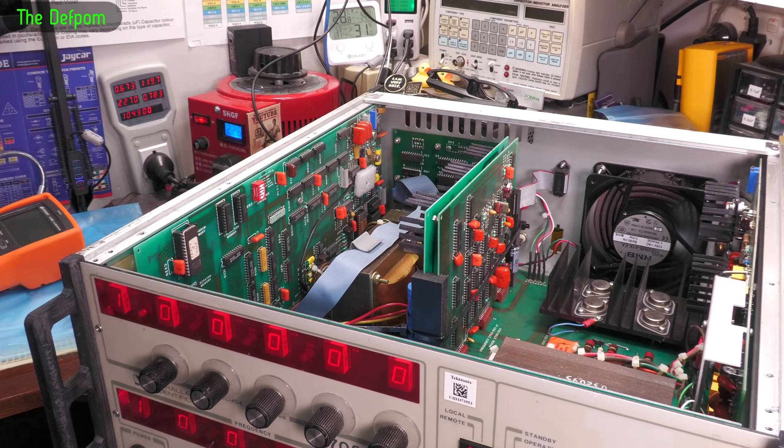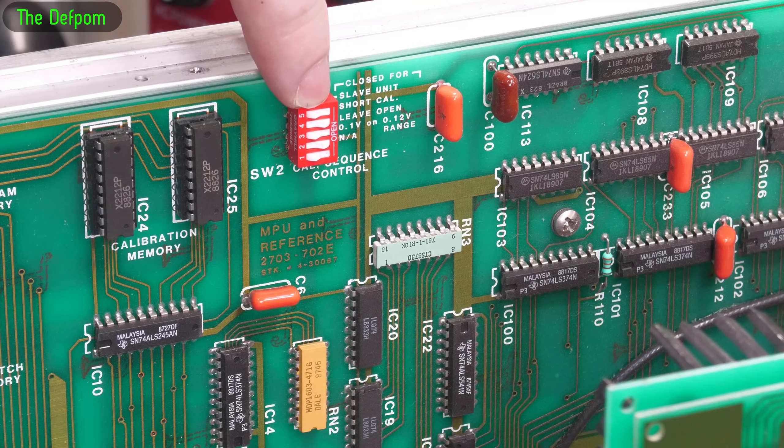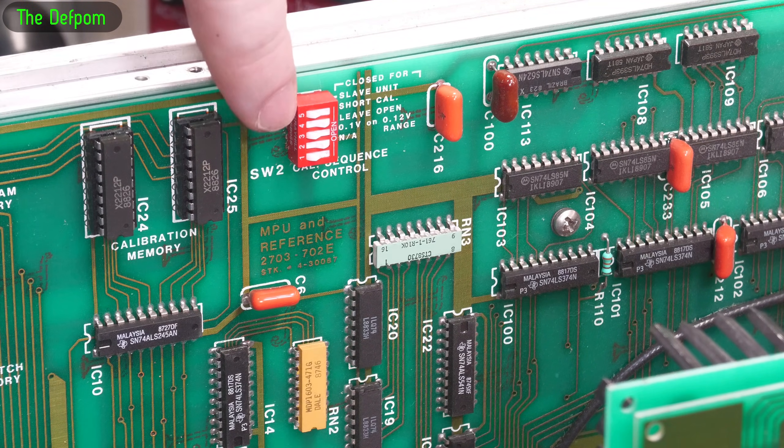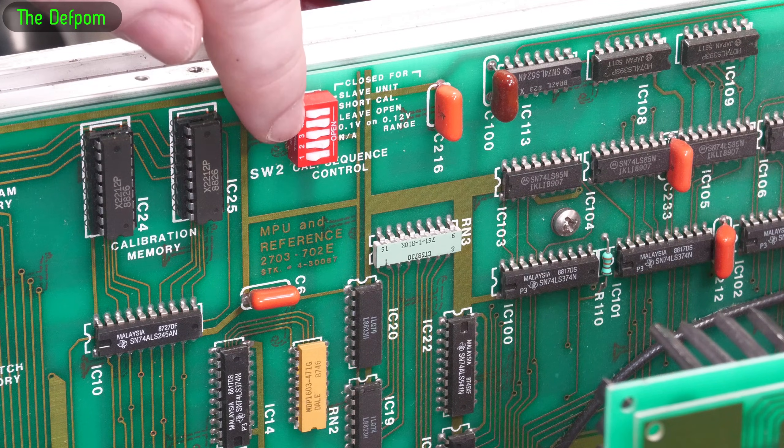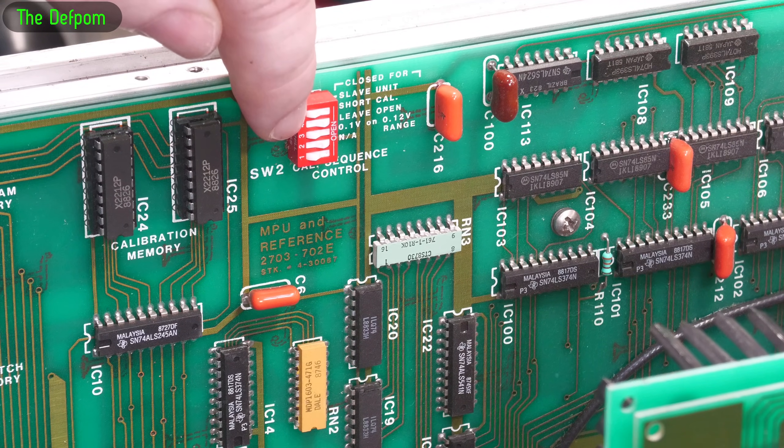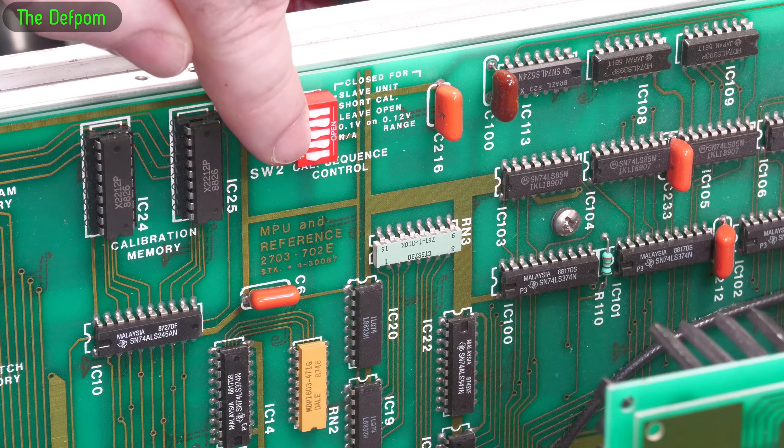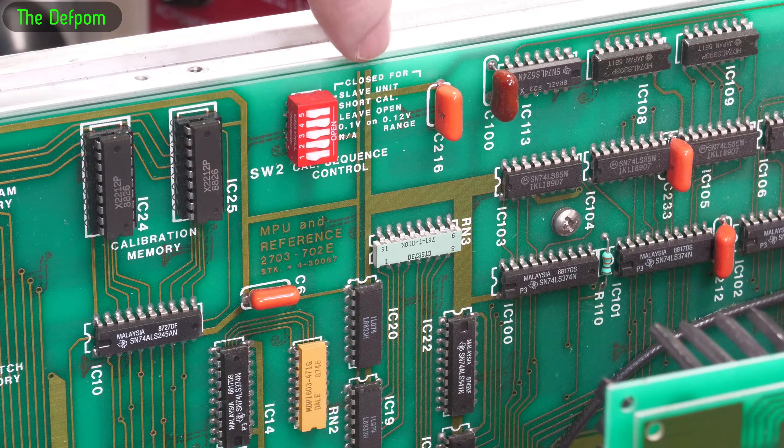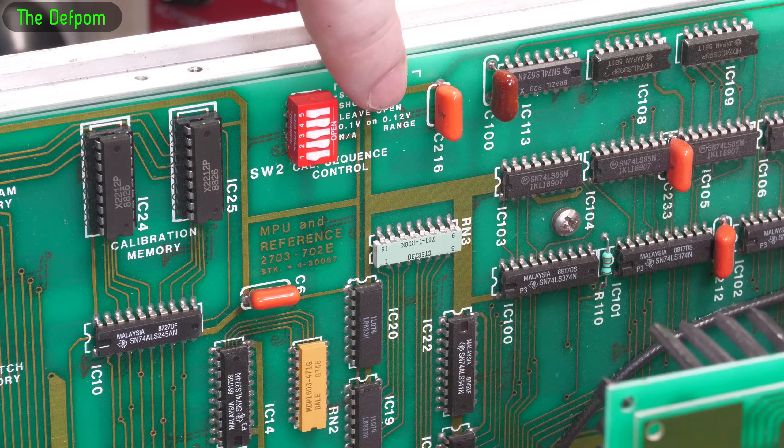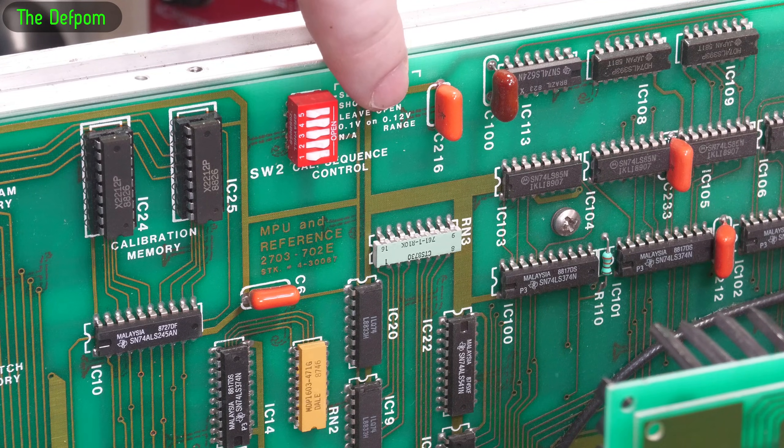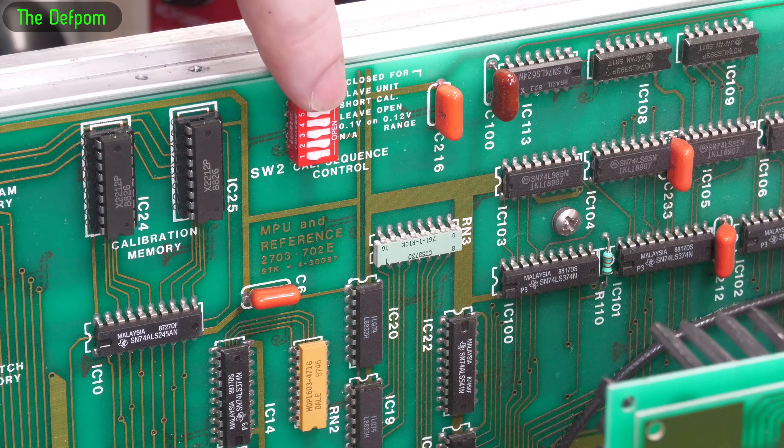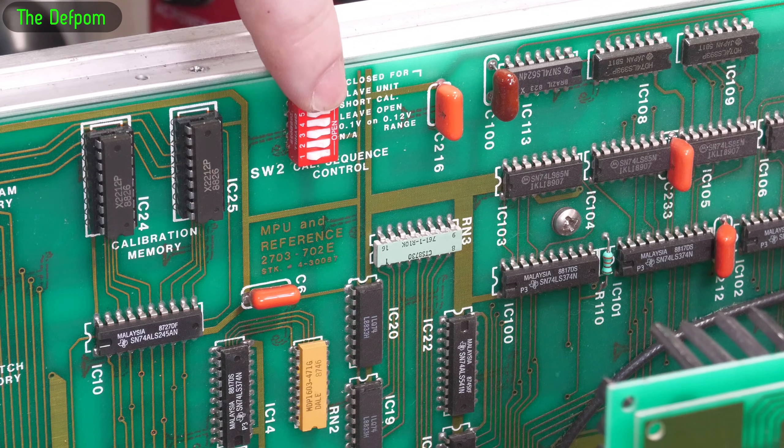Previously when I was doing the original repairs on this thing, I had 3D printed handles for it because it was all broken when I got it. There's a DIP switch just over here. Slave unit in this case should always be open. Short cal is closed. This is what I've been doing, short cal. That's five steps, one for each voltage range. Otherwise you leave it open. This other one here, which is currently closed, that's 0.1 volts on a 0.12 volt range.